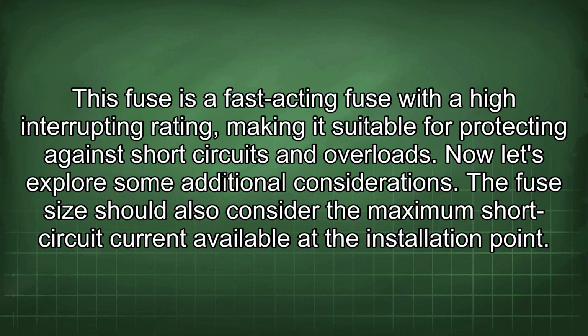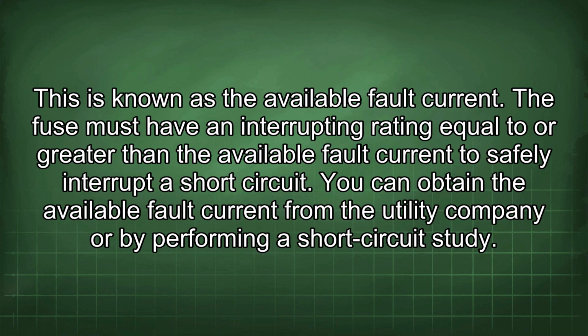The fuse size should also consider the maximum short circuit current available at the installation point. This is known as the available fault current. The fuse must have an interrupting rating equal to or greater than the available fault current to safely interrupt a short circuit. You can obtain the available fault current from the utility company or by performing a short circuit study.